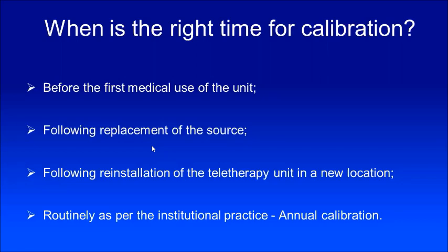Is that all? No. Most importantly, routinely as per institutional practice — that is, annual calibration. Some institutions do it every six months. We also do this very routinely — weekly and monthly — but there we use an ion chamber that was cross-calibrated against the one calibrated in a secondary standard dosimetry laboratory. We don't use the one calibrated in a secondary standard dosimetry laboratory for regular dose measurements, because that is something precious. We keep it and use another dosimeter cross-calibrated with it for our regular dosimetry verification.